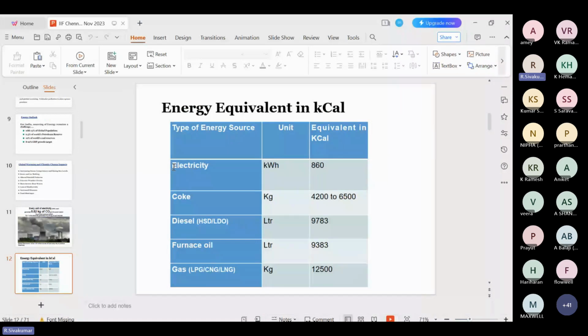If we are consuming 1 unit of electricity, it is equivalent to a calorific value of 860 kilocalories. For coal and coke, it is almost 4,200 to 6,500 kilocalories. It depends on the natural availability of the coal, whether it is taken from African coal, Indonesian coal or Indian coal. Normally, the Indonesian coal calorific value is somewhere between 5,500 and 6,000 kilocalories. So this value should be given by the supplier.